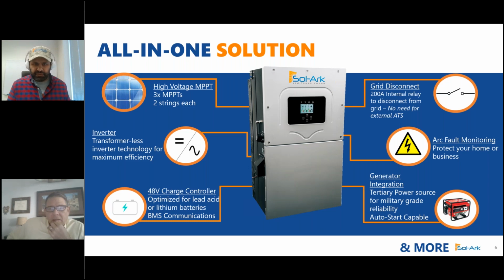And then, of course, the inverter itself is a transformerless high frequency inverter, which is highly efficient, about 97% efficiency. Again, built-in battery charger. So the battery controller, 48-volt charge controller, can handle, as David said, pretty much any chemistry, as long as it's in the charging range of about 48, it's a 48-volt nominal or 51.2 LFP nominal, and then a charging range of about 62 volts down to about 43 as the cutoff. And all that's built in internally. Nice big battery lugs, terminals that can hold up to 4-aught wire, actually 4 conductors. And it's got a separate breaker for each set of conductors, so you can actually divide up your battery bank a bit there. It helps with flexibility for sizing conductors.